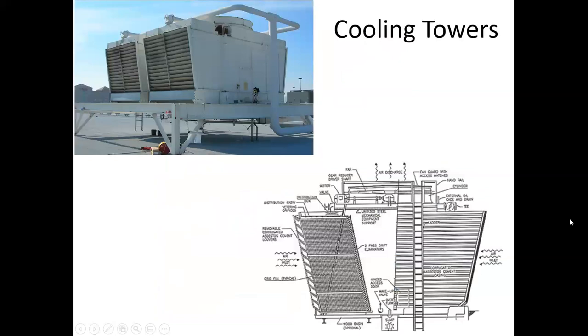Here's a picture of a cooling tower. They're going to sit outside someplace, with access to a lot of outside air. They work by evaporation as the primary mechanism. The water coming out of the condenser comes in this pipe and is distributed up in the top. There are basins up here, and little holes called nozzles in them. This water falls down through the fill and air is drawn across. We have a propeller fan that pulls air across. So this would be a cross flow tower, induced draft, because the fan is on this side sucking the air through. You can have forced draft towers where the fan's on the other side. This is probably the most common type.